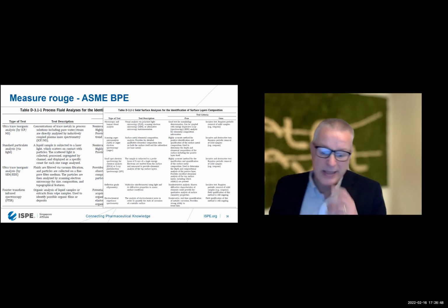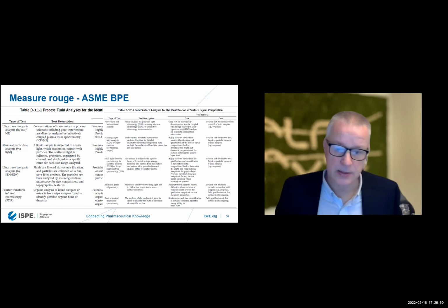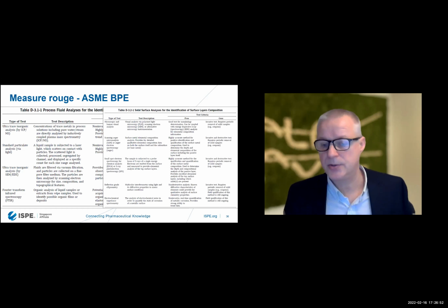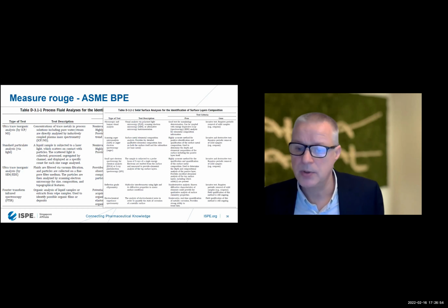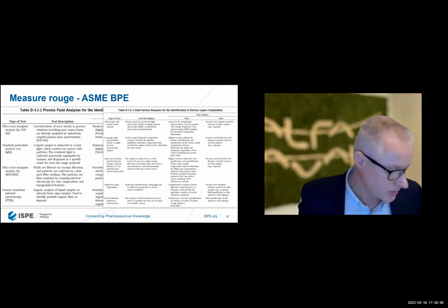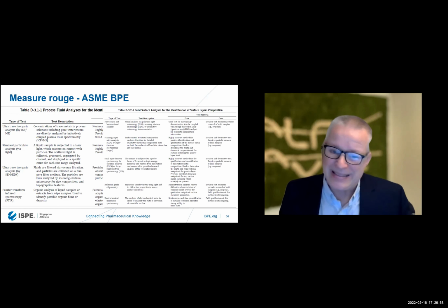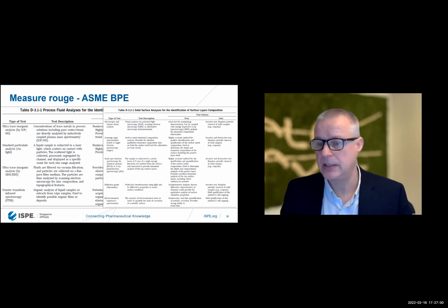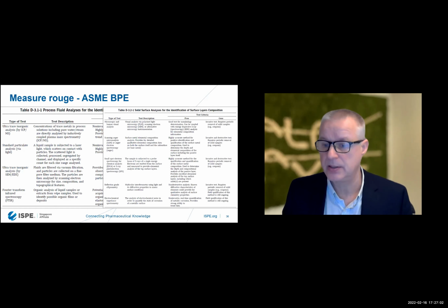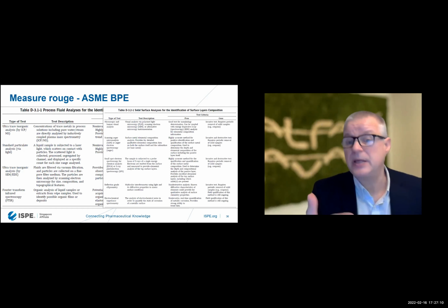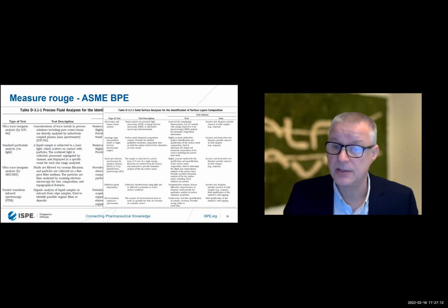Yes, there are tests, an indication, and also a natural explanation, because when you have ozone, or O3, that will speed up the rouge formation as well. The more oxygen you have in the system, the bigger risk you have of getting this ferrite oxide, or ferric oxide.